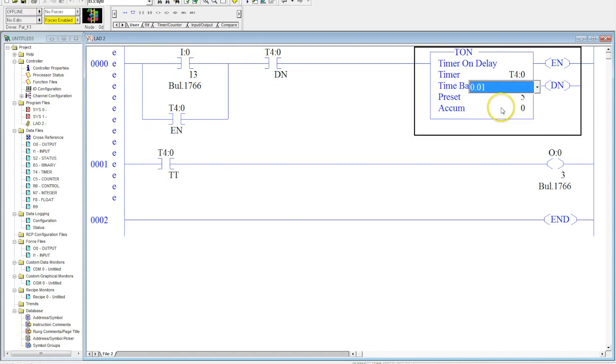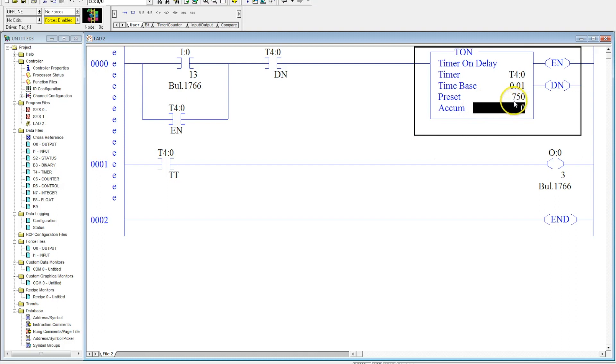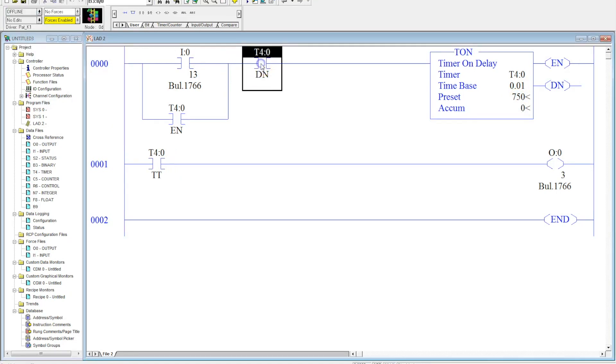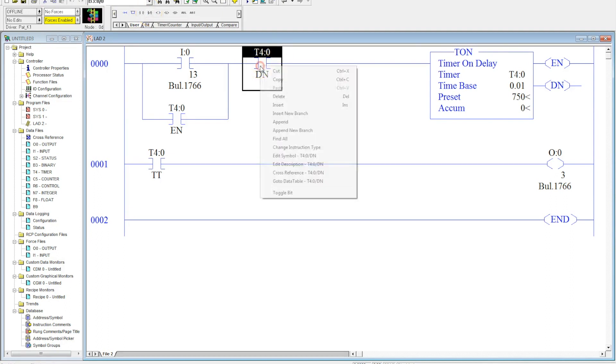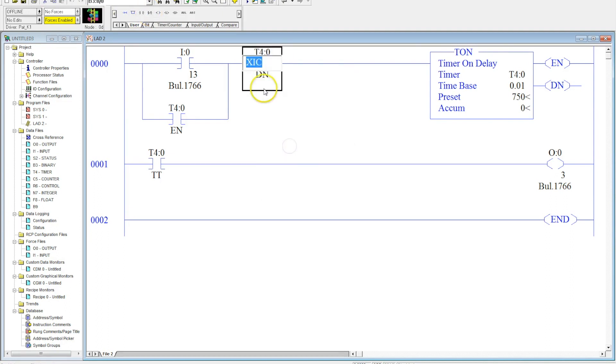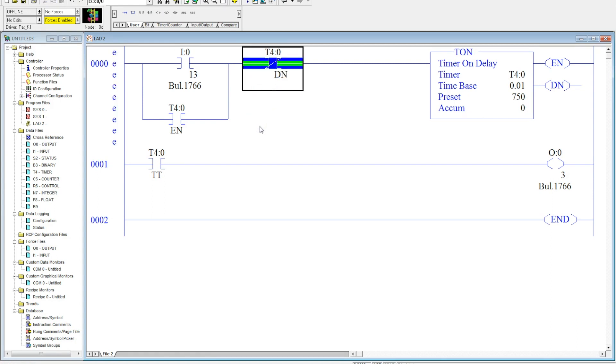So I'm going to let this run for seven and a half seconds, so I want that cylinder to be on for seven and a half seconds. So it's 750 multiplied by 0.01 which is 7.5. This needs to be a normally closed contact, I should mention that. Sorry, I put the wrong contact in here. I'm going to right click, change instruction type, change this over to XIO, examine if open instruction, and now it will operate correctly.